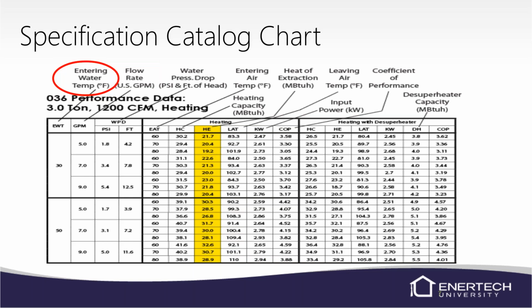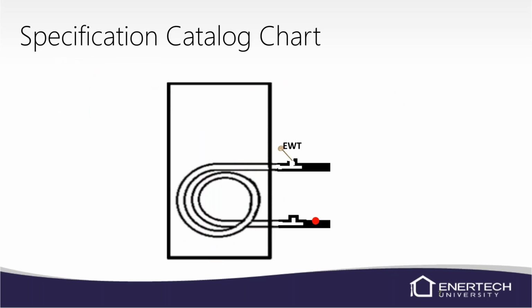And you've got heating capacities on one side, and normally you'll have another chart next to it for the cooling. So your heating and cooling will be all on the same page. But entering water is just that. This is your coaxial heat exchanger. It's just EWT, your entering water temperature.